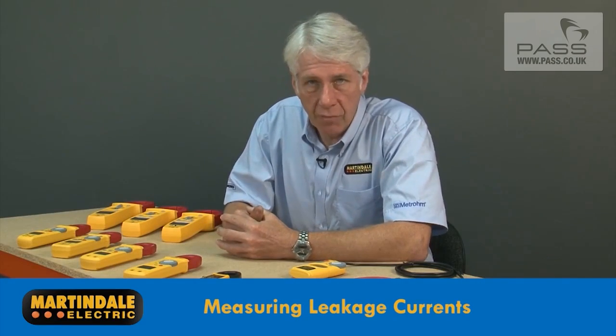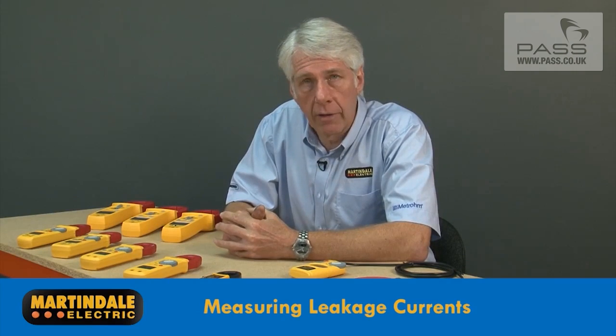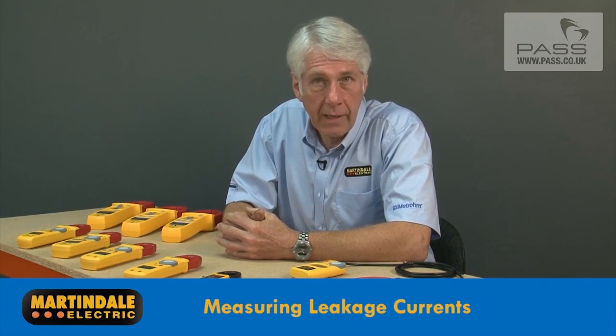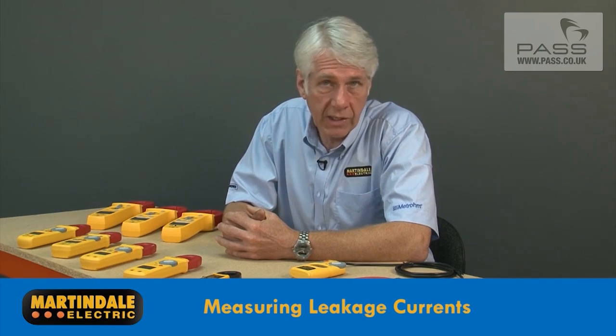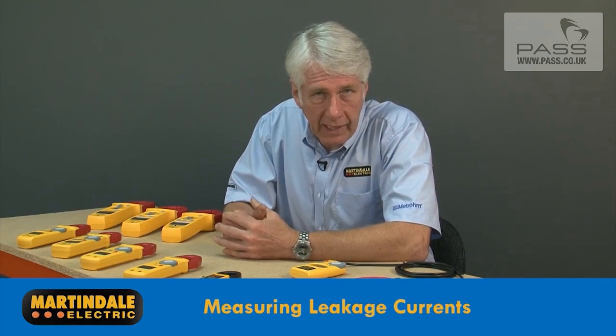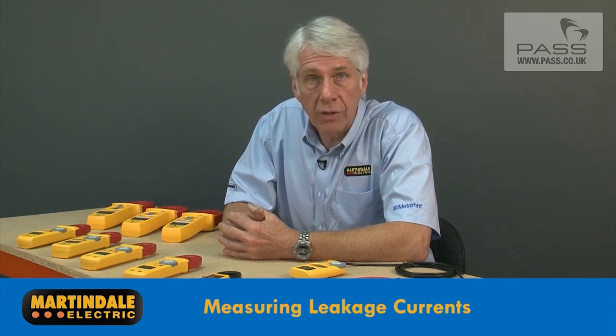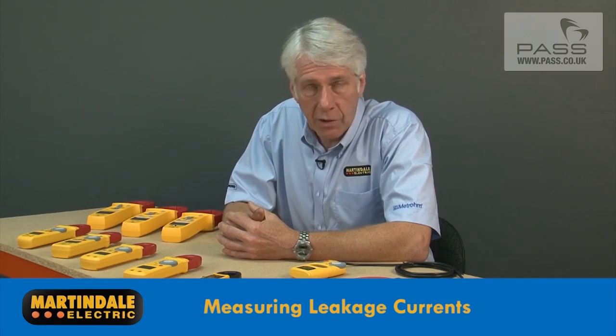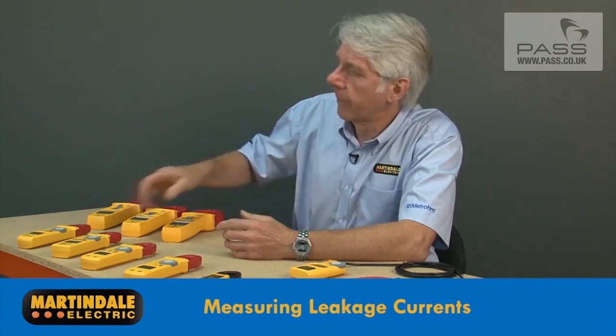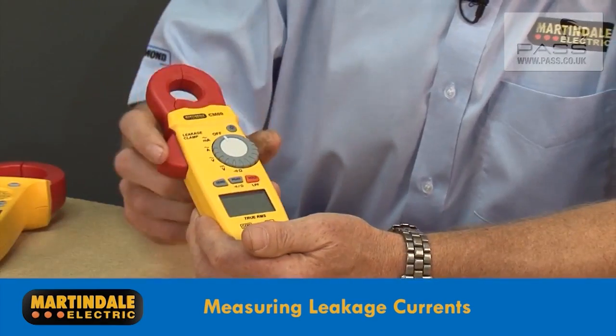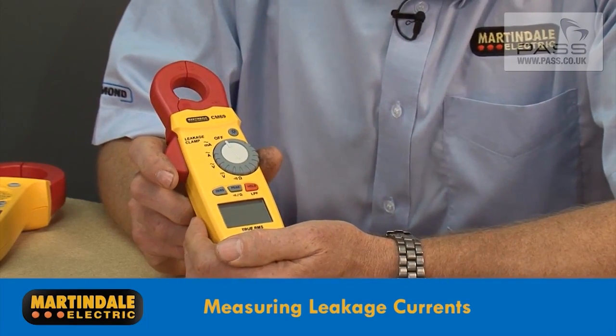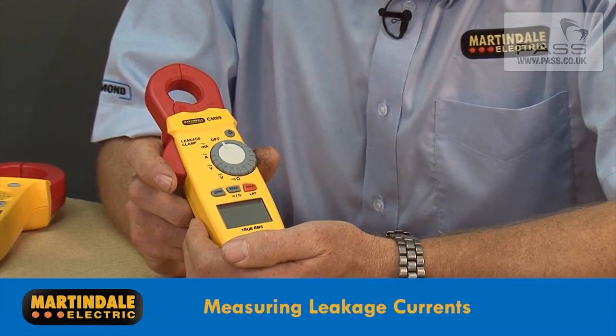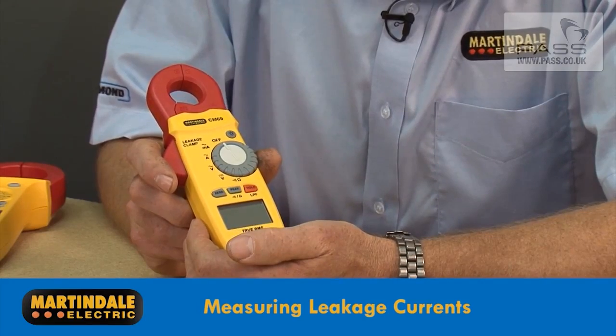The exception to this rule is when troubleshooting for leakage currents, typically at milliamp levels, and often the cause of nuisance RCD tripping. In this case, clamping around the line and neutral together will measure any imbalance caused by leakage currents. Now this requires the use of a specialist leakage clamp meter, such as the Martindale CM69, which is explained in another video.